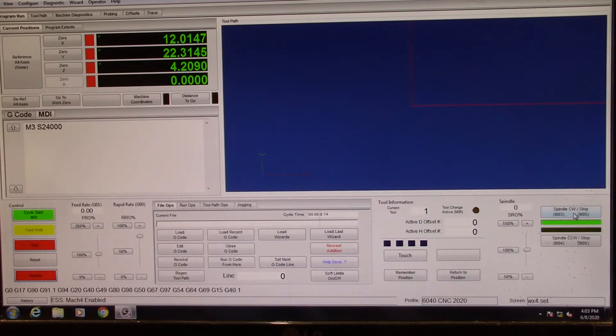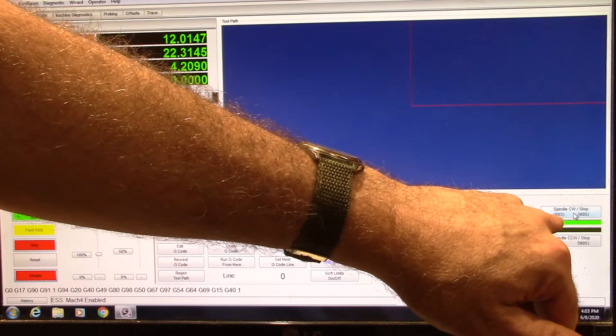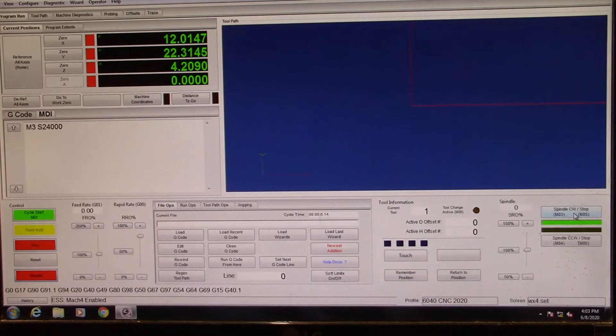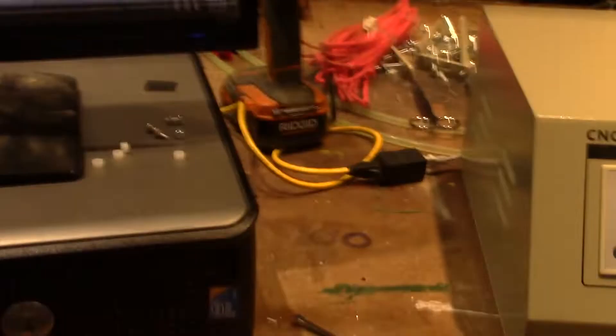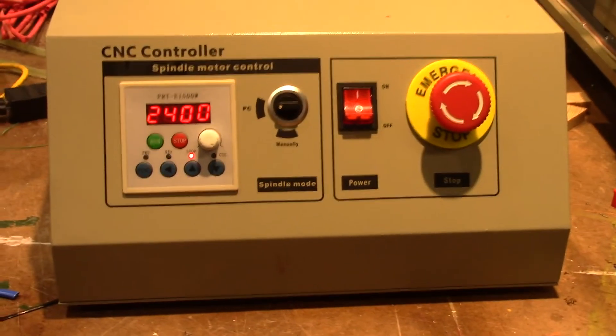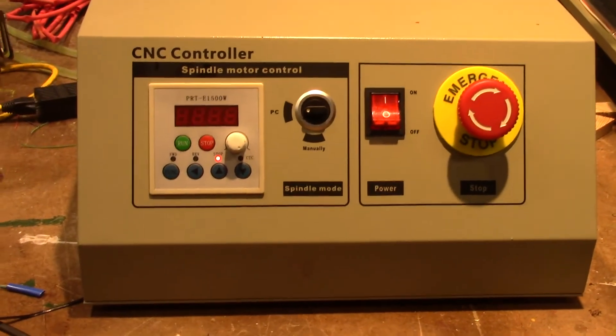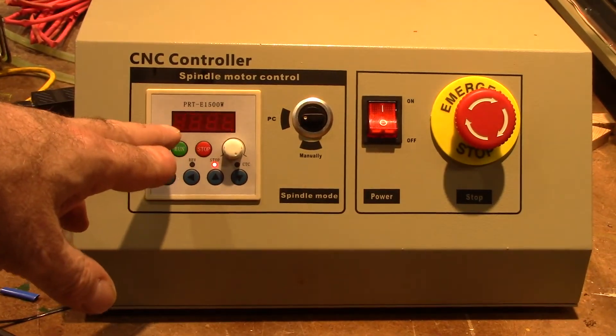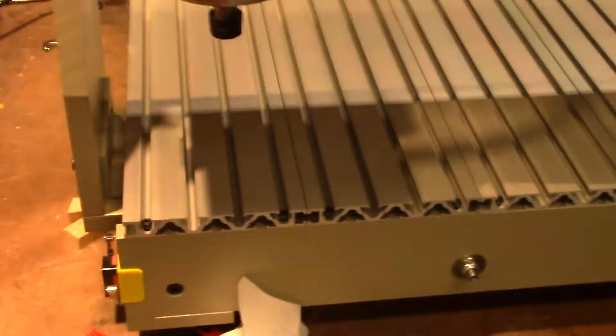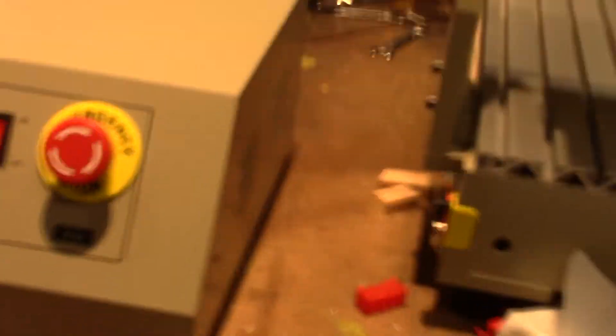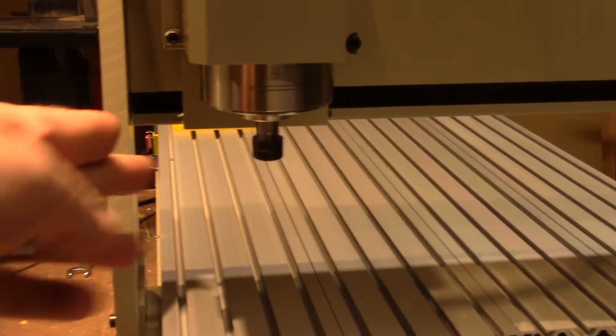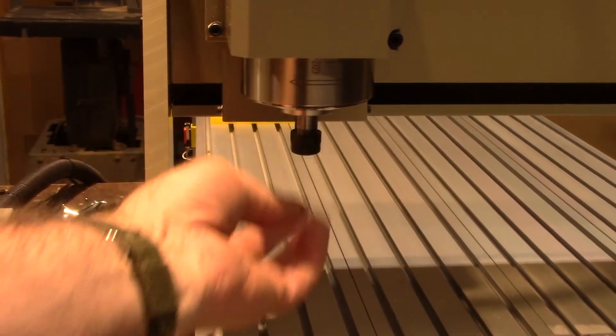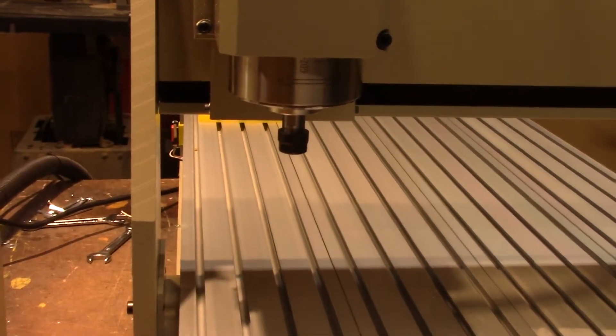Now this lit up, you see right there. Now let's go over here and look at the VFD. Now the VFD is blinking at 2400, but we still have a problem. Look over here. We've got no rotation. So we've still got no rotation out of our spindle.